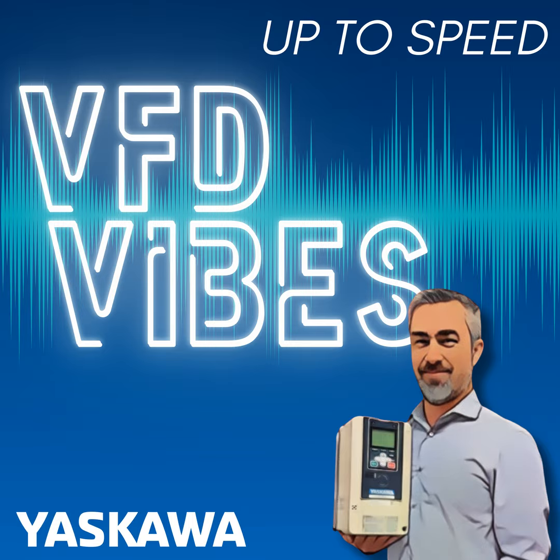One of the nice things about performing an auto tune, in either the stationary or rotational tune, and this is on Yaskawa drives now, is that you have to enter your motor amps. Your motor amps are probably the most important parameter that you're going to set on a startup because that's how the drive protects the motor. It has no idea what it's connected to. You have to tell it what size motor is on the drive. So if you can't remember, E2-01 is the parameter where we enter our motor amps, E echo 2-01. You can perform an auto tune and it's automatically populated in E2-01 when you enter your motor amps there.